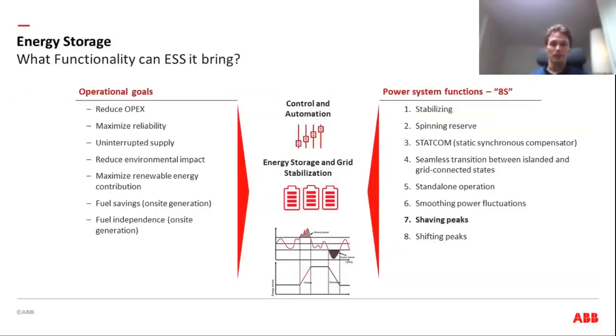So yes, basically that is what I said in the last slide. But energy storage can be used for more functionality than that. It can provide a stabilizing function, reducing the load change or rate of change of your demand, providing better voltage stability, for example. It can provide backup or spinning reserve power to your port. An energy storage system connected to AC is connected to power electronic converters that can also provide STATCOM functionality. So phase balancing and reactive power compensation. Well, the most important, or let's say lowest hanging fruit, obviously, is the peak shaving functionality.